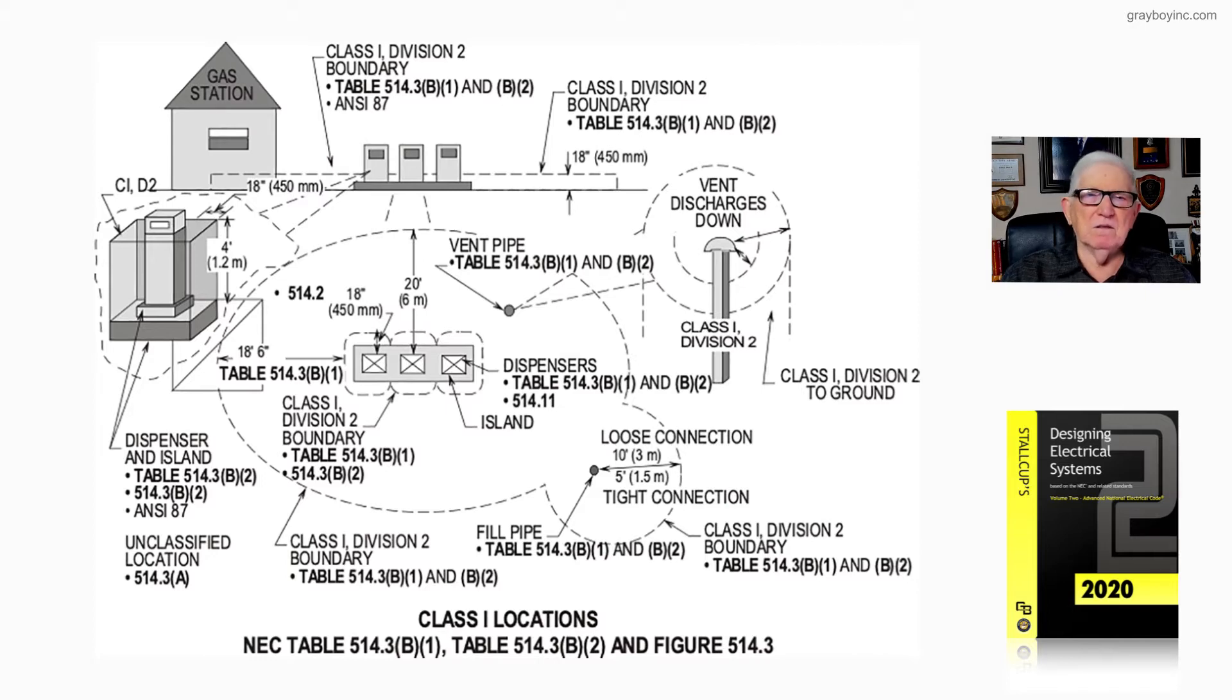Now notice in the gas station you see there, if they have a doorway there, and that room inside the filling station is not pressurized, or they don't have an air conditioning system to keep it well below the ignition temperature of gas or vapor, then the inside is a Class 1 Division 2, 18 inches as you see there as it extends out, 20 feet.